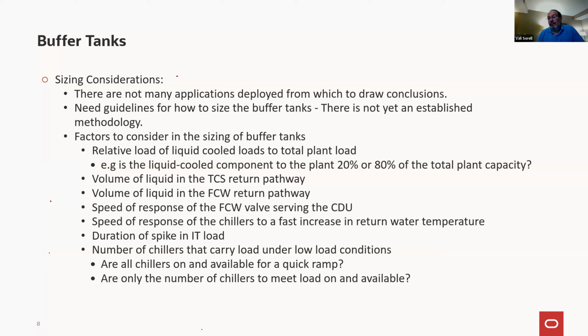And also, finally, an important aspect, you may have 20 chillers to take on the load. Right now, you have 8 chillers running, 12 idle, and the load hits. To start those chillers may take a few minutes. If you have 18 or 19 or 20 chillers, even at low load, they'll ramp up much faster and be able to respond more quickly.